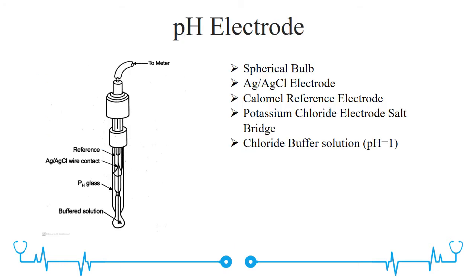Next comes the pH electrode. The glass electrode is normally used as a pH electrode. It consists of a spherical bulb of 0.5 cm in diameter which provides a thin glass membrane that permits the passage of only hydrogen ions in the form of H3O+ ions.